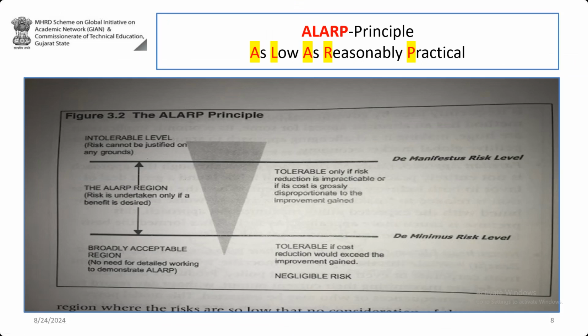So you are gaining from making the system SIF from SIL 1 level to SIL 3 level, but the cost which you will be spending to make it SIL 3 level is so high that probably you will lose all your profit. So government or court of law has said it, make it as low as reasonably practicable. Make it SIL 1, it is reasonably practicable to accept SIL 1. Making SIL 1 to SIL 2 is costly. For a SIL 1 system, you may need a single transmitter, single logic solver, and single final control element, which are the three major elements of a safety system.